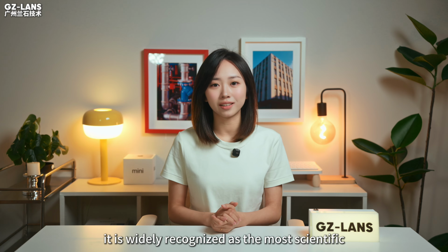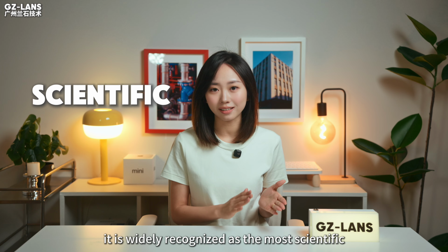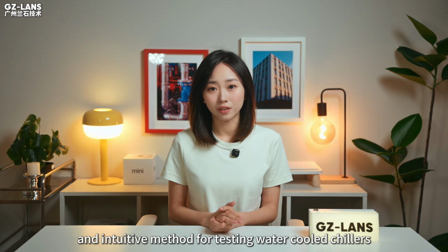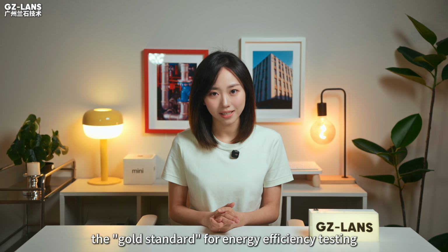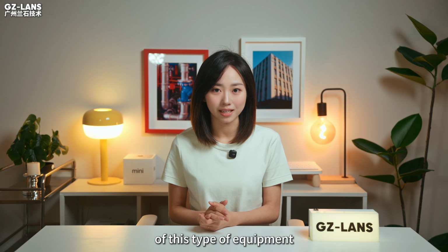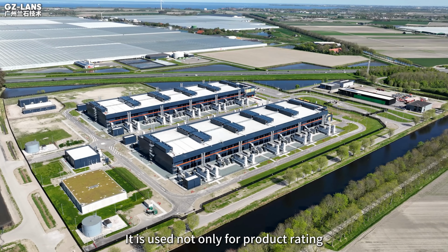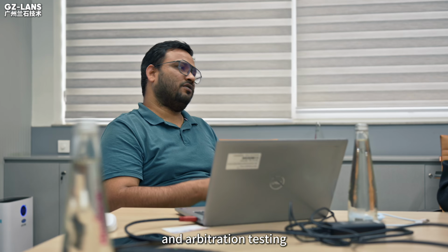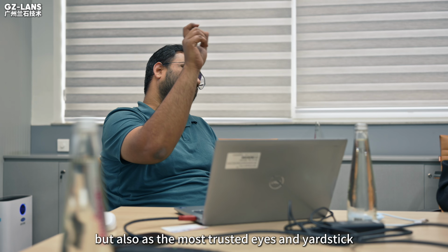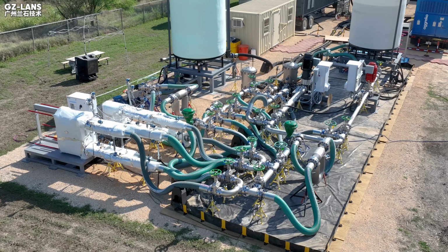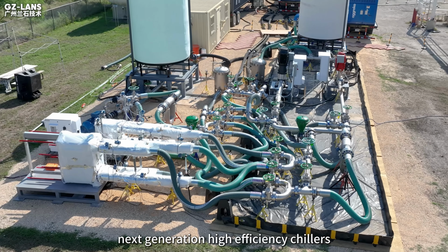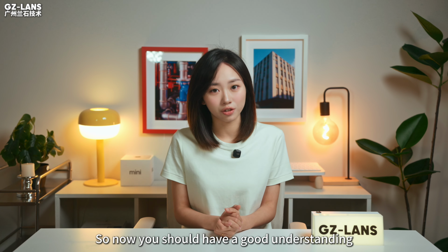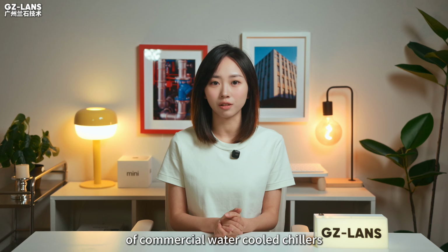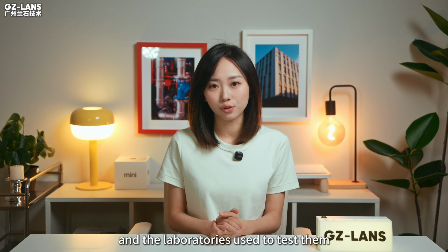Therefore, it is widely recognized as the most scientific and intuitive method for testing water-cooled chillers, the gold standard for energy efficiency testing of this type of equipment. It is used not only for product rating and arbitration testing, but also as the most trusted eyes and yardstick for engineers developing next-generation high-efficiency chillers. So now you should have a good understanding of commercial water-cooled chillers and the laboratories used to test them.